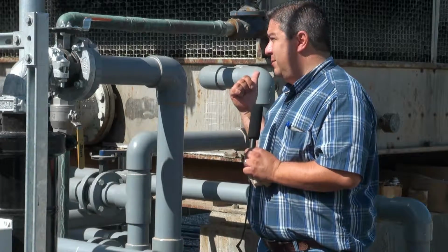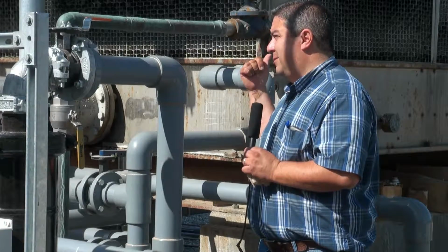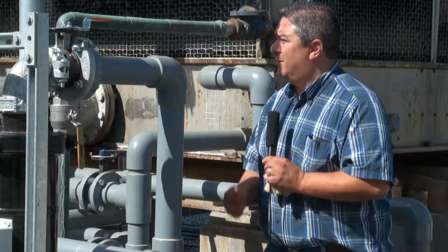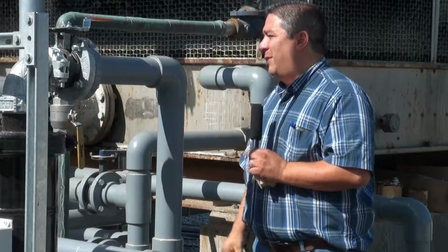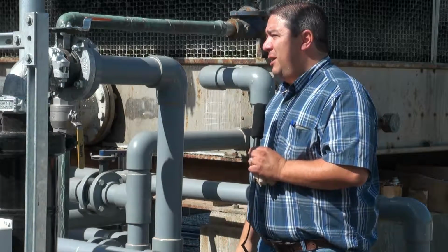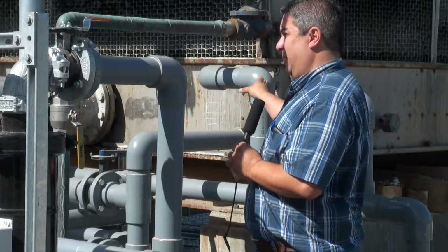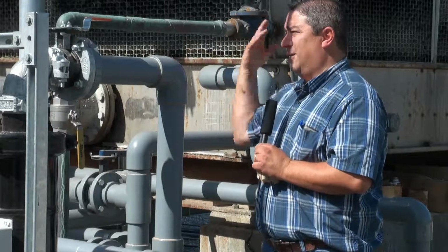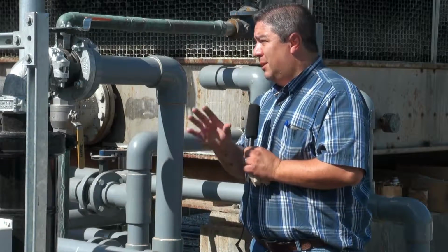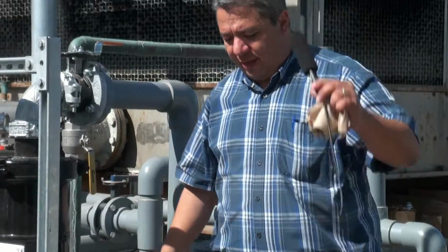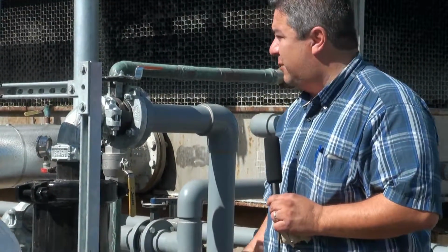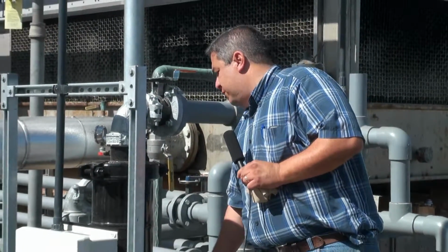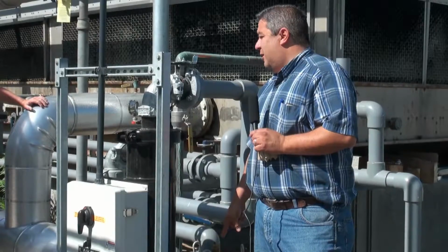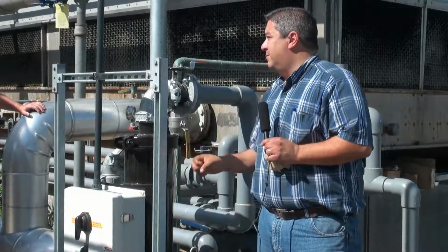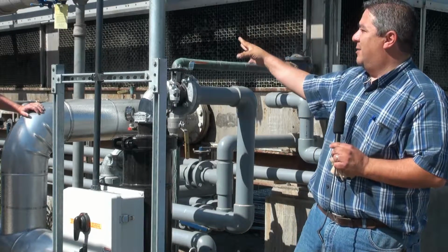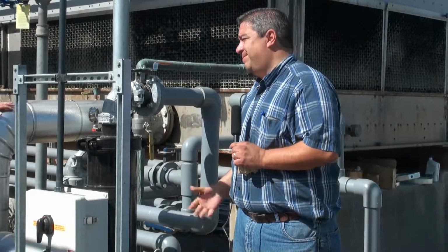You know, I've seen 15 gallons of crap coming out of those towers at the end of the year from people with a shovel. You're in there with a shovel, all right? I saw a guy with a shop vac trying to clean it all up the other day. So be careful. As long as you keep it healthy, which keeps the pumps healthy, whatever it takes. And like I said, they have other options for this Lakos separator if you ever want to. They're expensive options to do automatic blow down. They'll remove this SRV and put a ball valve right here, and automate the ball valve with a relay that flushes out every midnight for 30 seconds. People don't like it a lot because they don't like the wastewater.